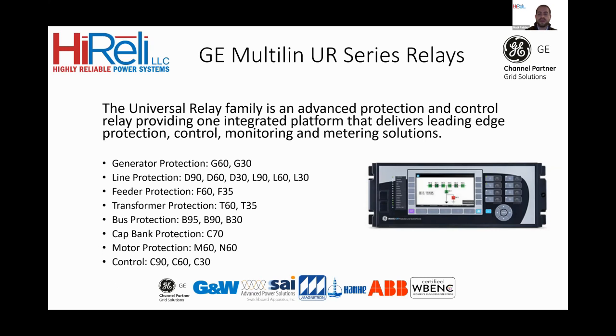Some of the UR features: they have modular construction and common hardware, leaving you with a reduced stock of spare inventory. So the power supplies, CT/VT cards, IO modules, etc., are all draw out style when you open up that relay case. They offer digital fault recording and sequence of events recording. There's a large HMI and annunciator panels that can be built on the front. The flexibility and customization of these products make this easily suitable to retrofit almost any of your legacy P&C schemes that you may have. And these also have enhanced cybersecurity features such as password complexity, including meeting and exceeding NERC CIP requirements, AAA server support, role-based access control, and event recorder for syslog.